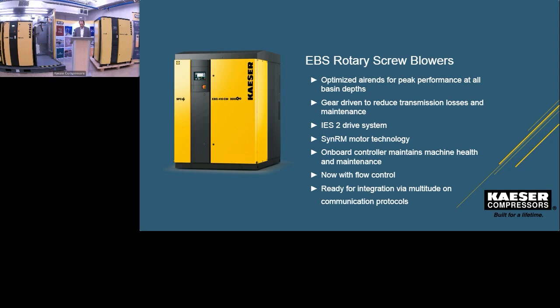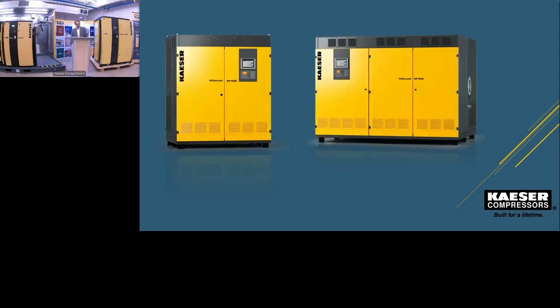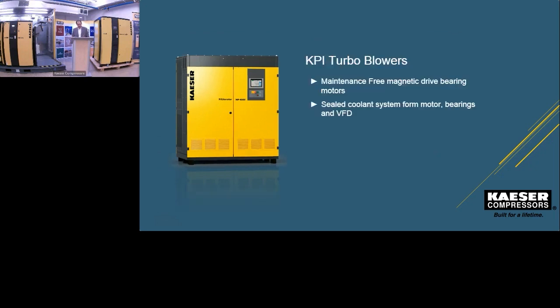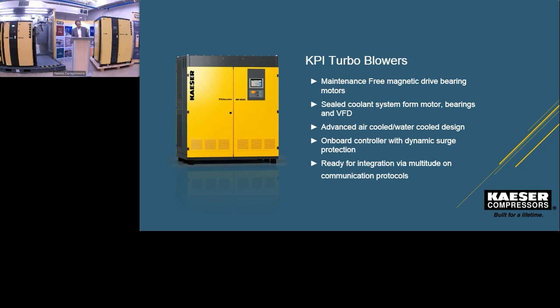The next thing I'd like to talk to you guys about is the new KAESER turbo blower. This is something new for us at KAESER that we've gotten into in the past year. It is a high-speed turbo blower package, so the impeller, of course, is directly mounted to the motor itself. That motor, as I mentioned, I was talking about, this is a permanent magnet motor. So again, this had a synchronous reluctance motor, and our turbo blower has the permanent magnet motor.